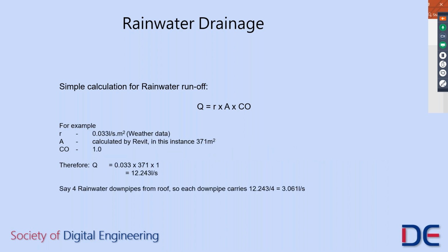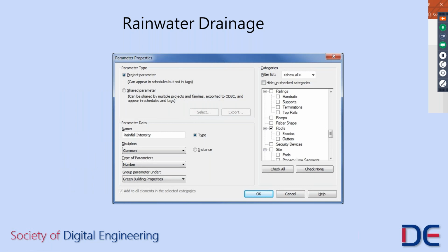So in this particular instance, we're saying we have a rainfall intensity, my apologies, of 0.033 liters per second per meter squared. The area is calculated by Revit, in this particular instance, 371 meters squared, and our coefficient is one. So this can give us that sum you can see before you. If we want to divide that by the number of rainwater downpipes, we can do that as well. And this is giving us just over 3 liters per second per downpipe if we have 4 downpipes in our design. To do this, what we need to do is to include the parameters as we have with all the previous ones. So we can apply the rainfall intensity to roofs, which allows us to use it in a roof schedule.